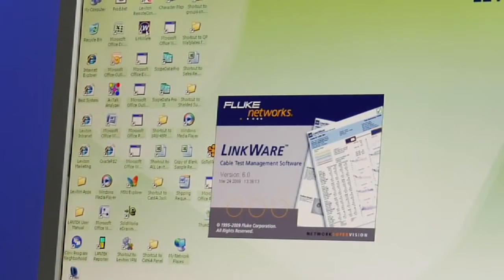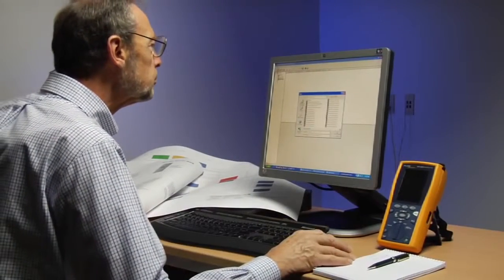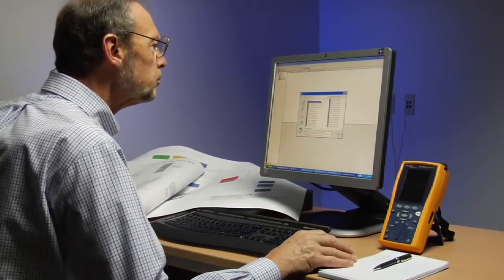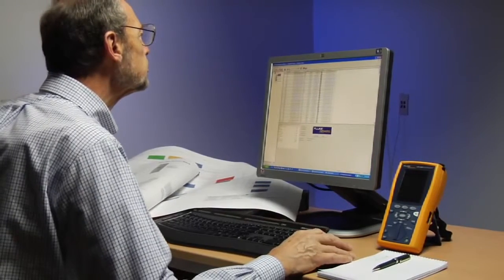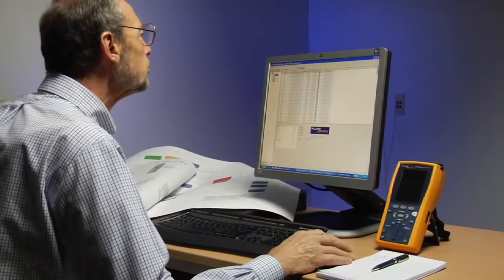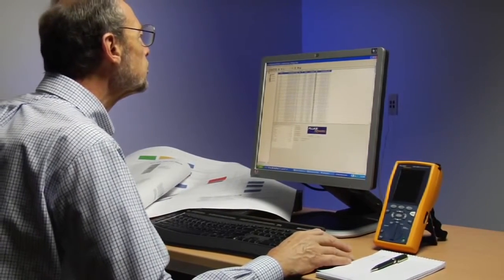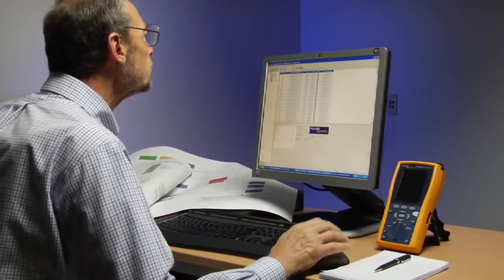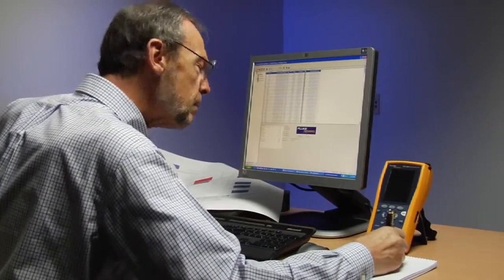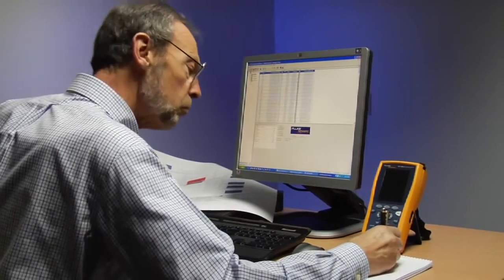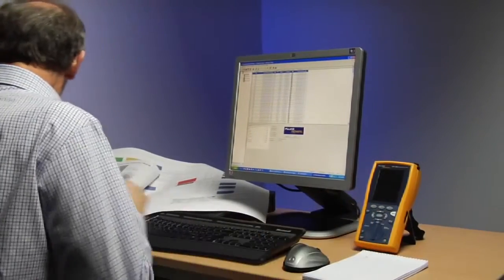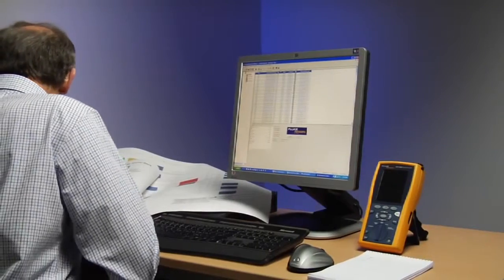The first step is to determine which links to analyze. It's not necessary and would be extremely time consuming to evaluate the influence of every link in the cabling installation on every other link. Instead, we'll follow a sampling plan to determine how many links should be tested. In this example, we're going to select five links for analysis.